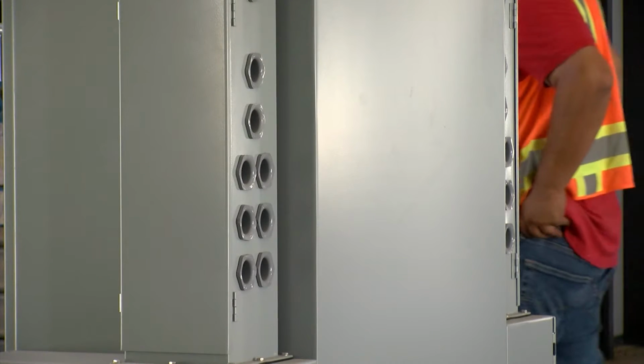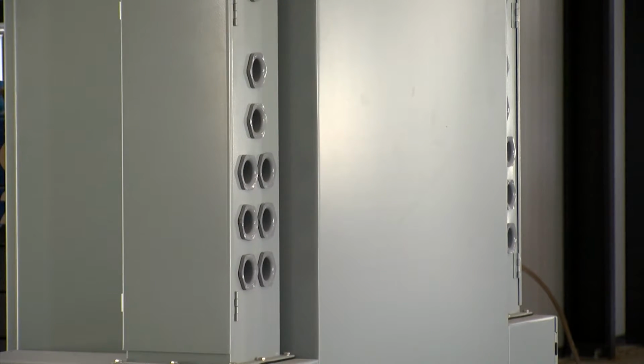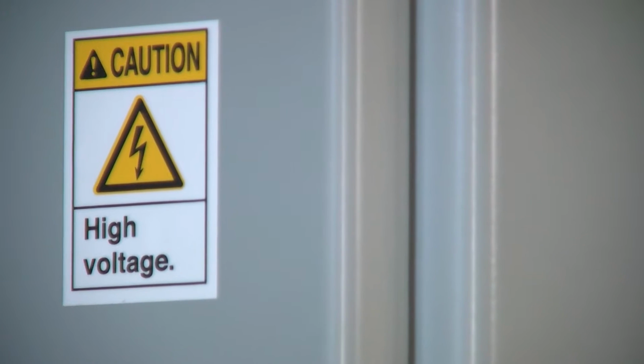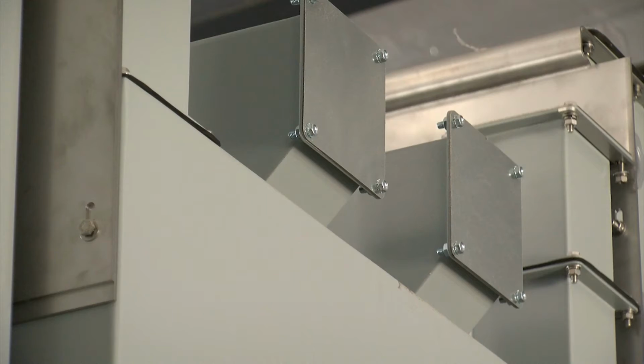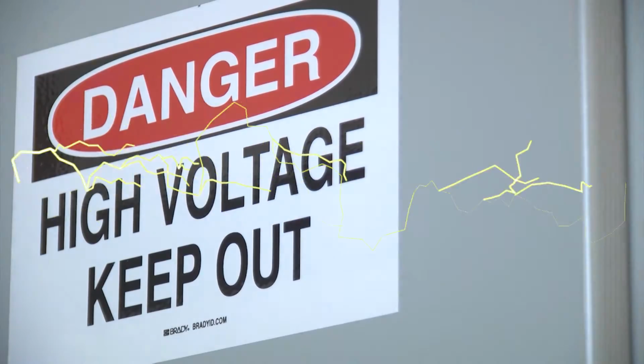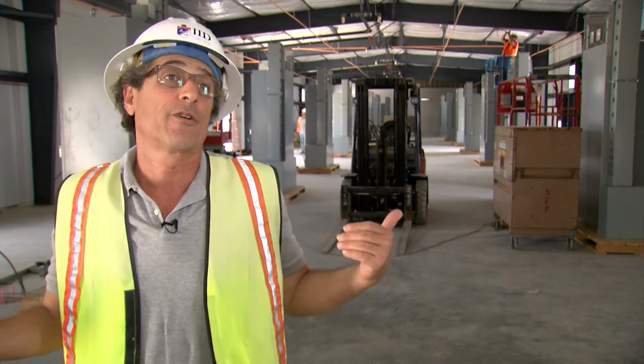Operators can release up to 20 megawatts of that capacity in an hour. Townsend says that's a pretty big stream of electricity, and the batteries don't have to warm up before they can deliver the juice. Everything takes time to cycle, especially steam turbines, since you have to boil water. Combustion turbines, or gas turbines, do speed up, but it takes anywhere between 5 to 20 or 30 minutes, depending on the model, to come up to full speed.